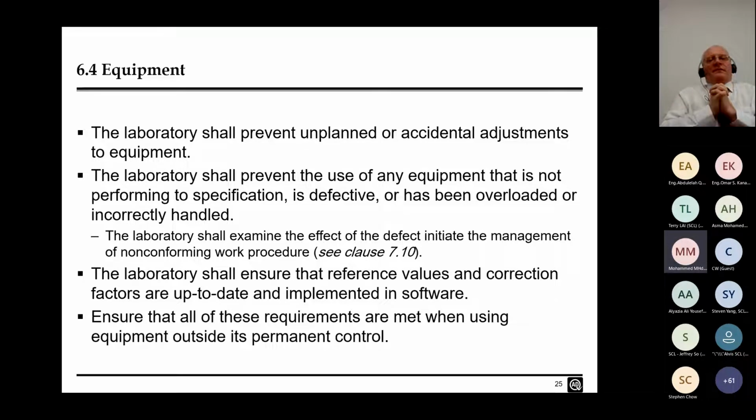Sorry, can I ask a question? Yes. What do you think about if the calibration is done by a third-party entity? So when you send something out for third-party calibration, when it comes back, you should be checking that it's working properly. My advice would be that you should do some checks before it goes out and when it comes back.